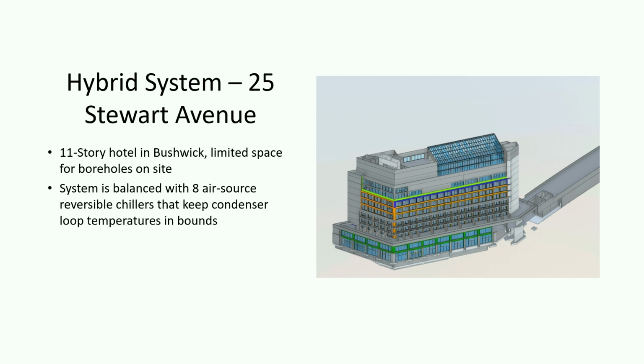25 Stewart Hotel in Bushwick. Again, significantly higher cooling loads than heating loads. And we have the very eloquently named rat tail on the corner of this building where our boreholes are drilled. We don't have any space to expand that bore field. We're very limited. We're stuck in our little spot. So in order to keep the balance in the system, we have a system of 8 air source reversible chillers that come online to meet any cooling loads that our geothermal system is not able to keep up with.